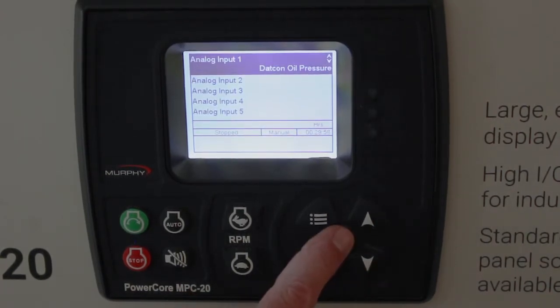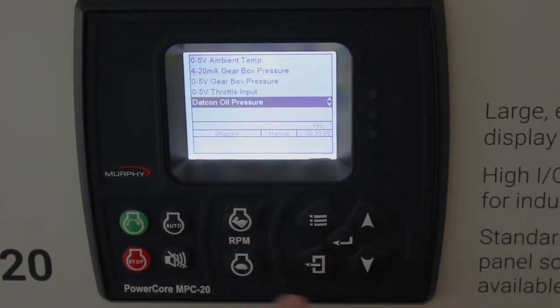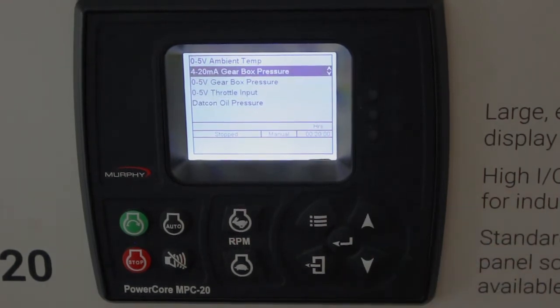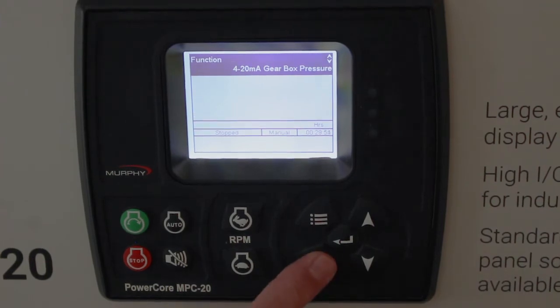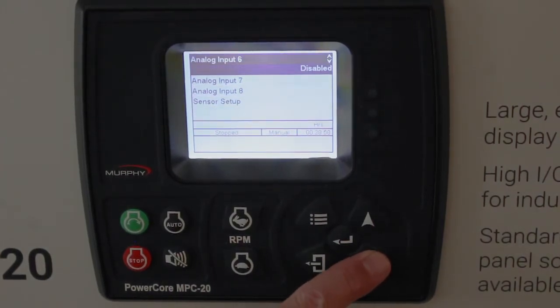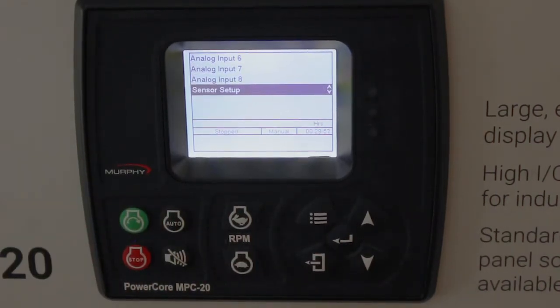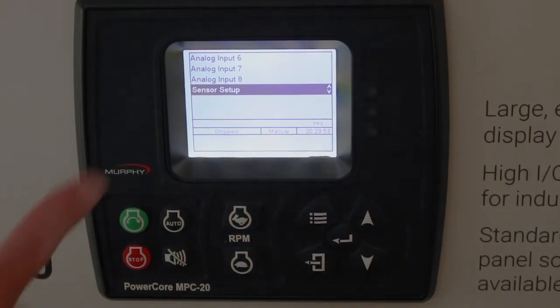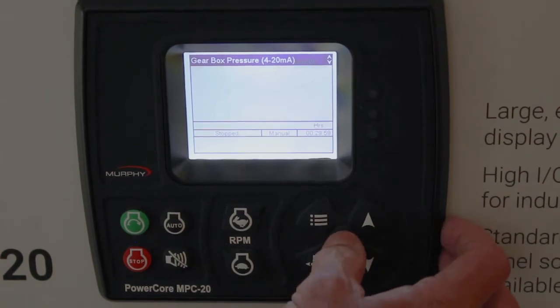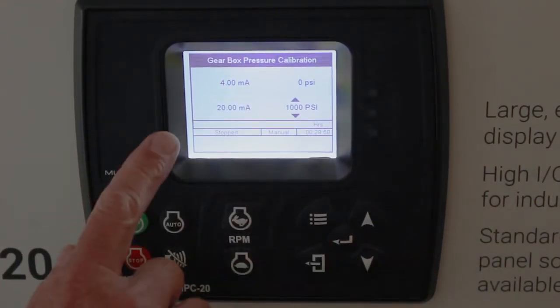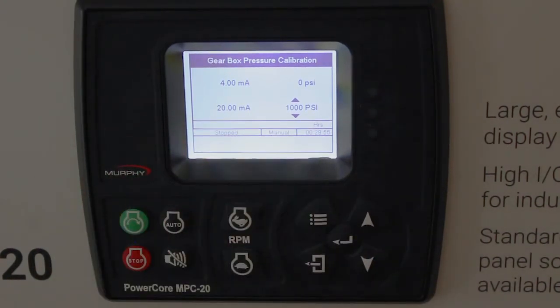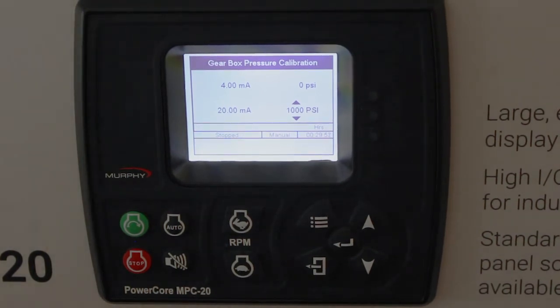If you change analog input one to a four-to-20 input — say, gearbox pressure — we don't have the lookup table for that built into the controller. So at the end of the analog menu there's a sensor setup. When you choose a zero-to-five or four-to-20 analog input, this sensor setup appears. Hit enter, because you have to tell the controller what four to 20 milliamps means. Four milliamps generally equals zero; 20 milliamps in this case would equal a thousand pounds. From experience, gearbox oil pressure isn't going to be a thousand pounds, so you would lower this to what 20 milliamps represents. That way we're calibrated and linear in between.